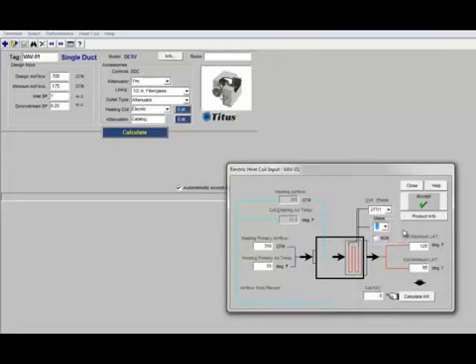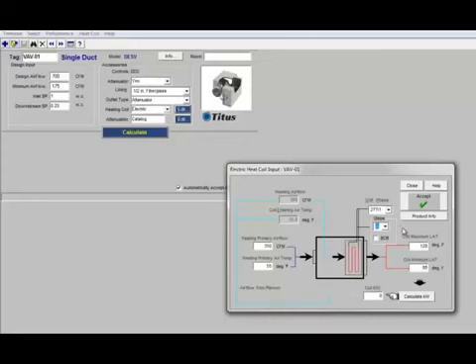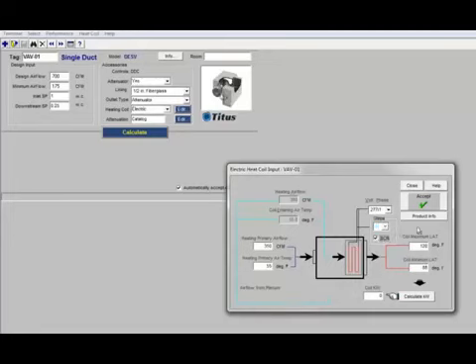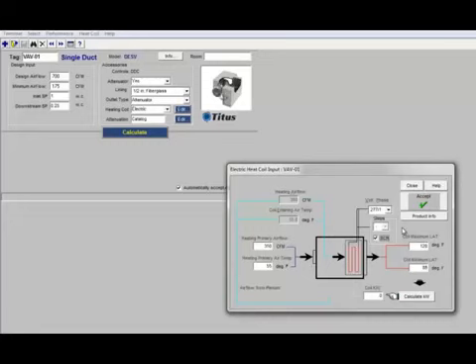Sometimes we're asked if we can build a ten-stage heater. That's totally impractical because it would require ten separate elements and all the controls to operate each of those elements. When situations like that come up, it's best to suggest an SCR controlled heater. An SCR heater gives us the same functionality we would get from an infinite number of stages of heat, so that gives us the ultimate in control.